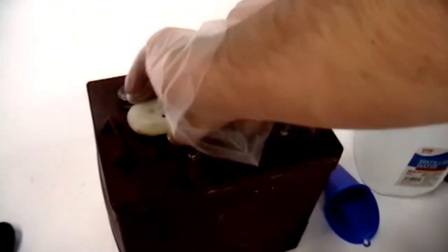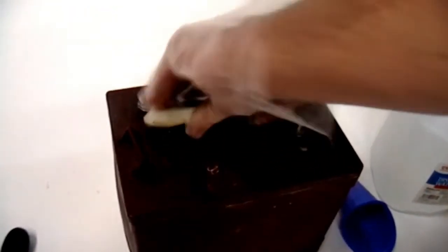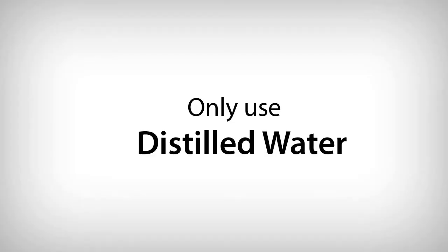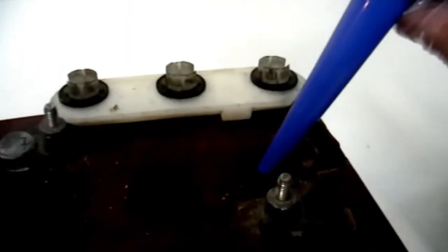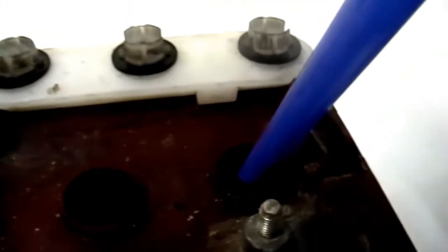On flooded or wet batteries, check the water levels. The water level should be high enough to just cover the plates. If water is needed, only use distilled water and do not overwater as it can spill and the electrolyte is very corrosive.